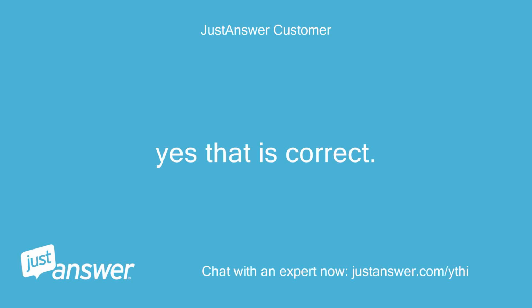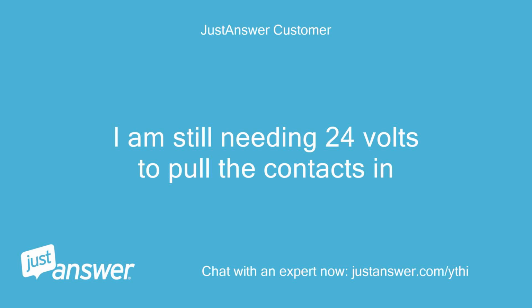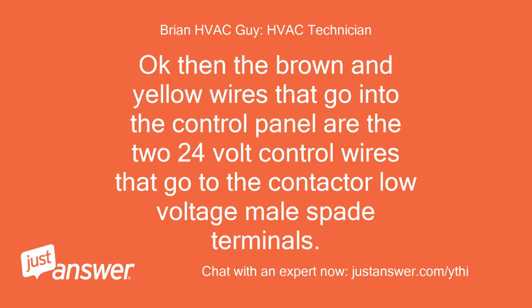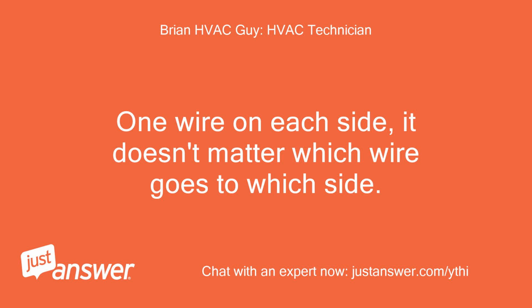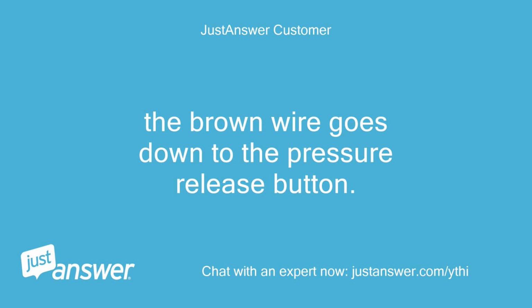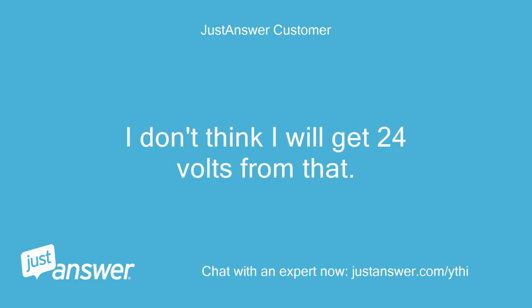Yes, that is correct. I'm still needing 24 volts to pull the contacts in. Okay, then the brown and yellow wires that go into the control panel are the two 24-volt control wires that go to the contactor low voltage male spade terminals. One wire on each side, it doesn't matter which wire goes to which side. The brown wire goes down to the pressure release button. I don't think I will get 24 volts from that.